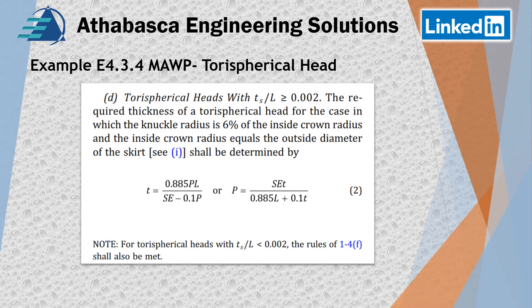Now we'll look a little more closely at the torispherical head and the definition pulled right from Part D about how to calculate the thickness. There are some conditions — for example, the thickness over L has to be greater than 0.002. The required thickness of the torispherical head for the case where the knuckle radius is 6% of the inside crown radius, and the inside radius equals the outside diameter of the skirt. You can calculate this in terms of thickness or in terms of pressure.